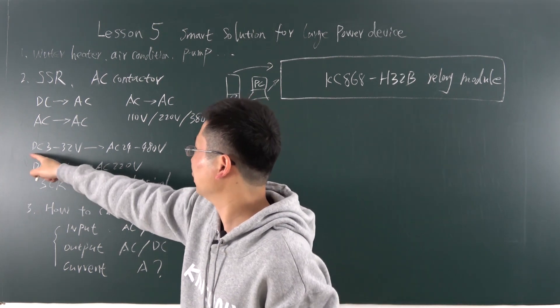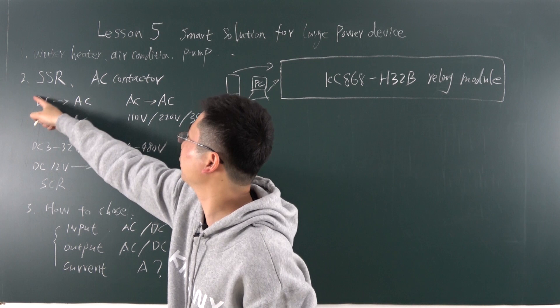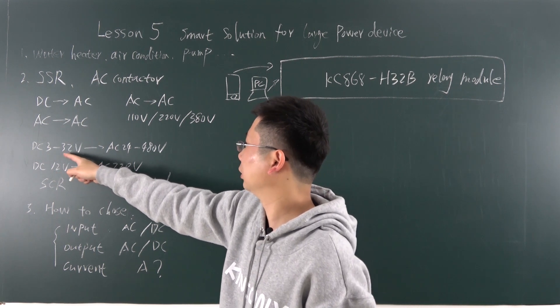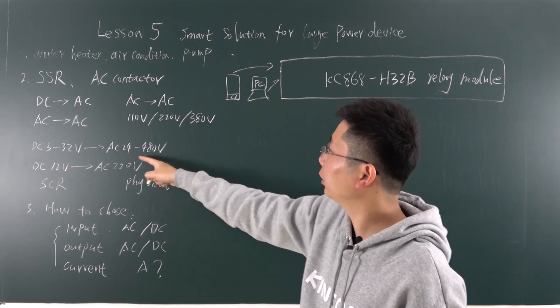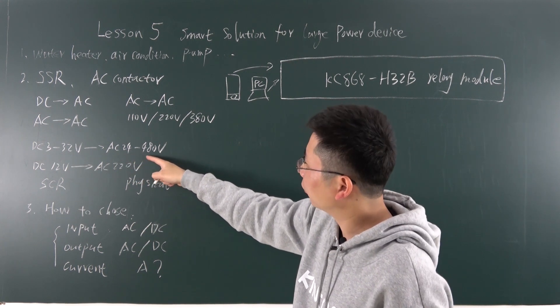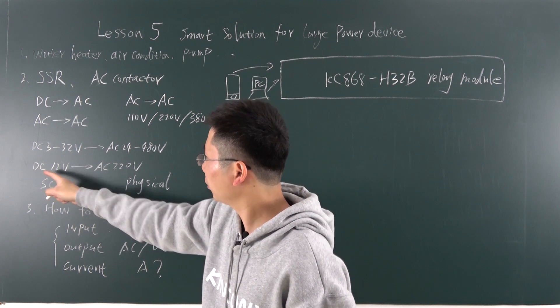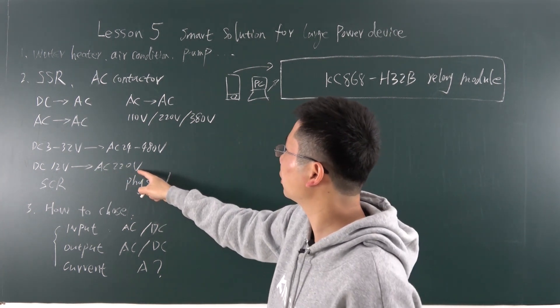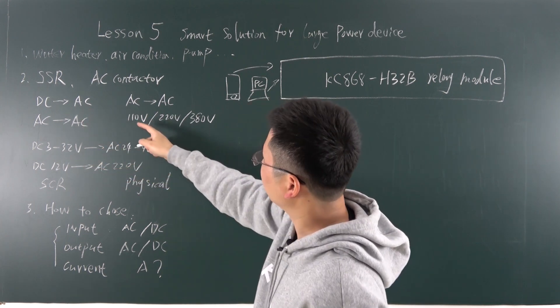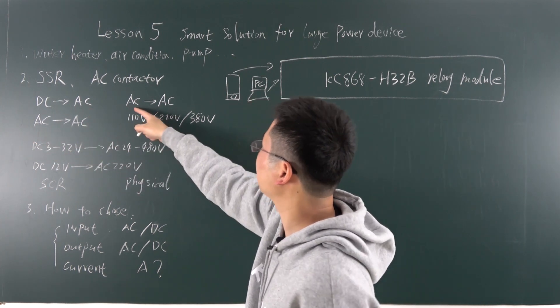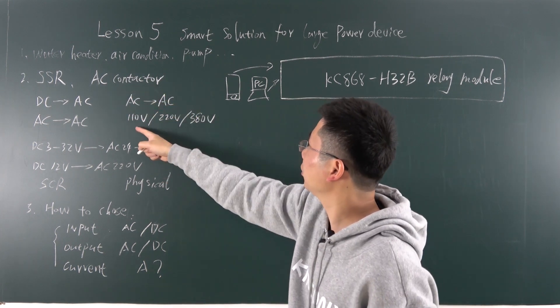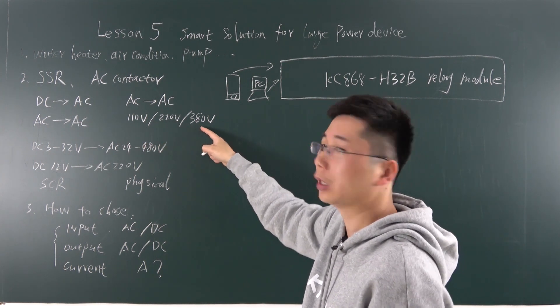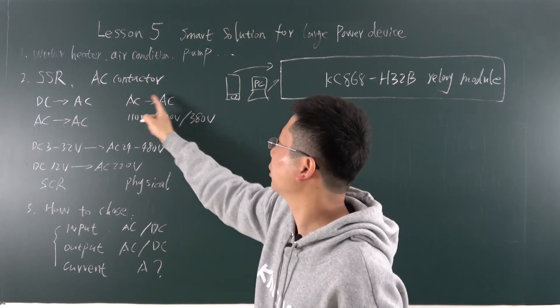And the typical one is, if you have input, for example, this type. If you have input from 3 to 32 volt, and it can control the AC output is 24 volt range to 480 volt. We can use input is 12 volt DC to control the AC 220 volt. This is for the DC to control the AC. But if you also have the AC to control the AC type, just like this AC contactor. So we can use the AC for 110, 220, or 380 volt to control the AC output.